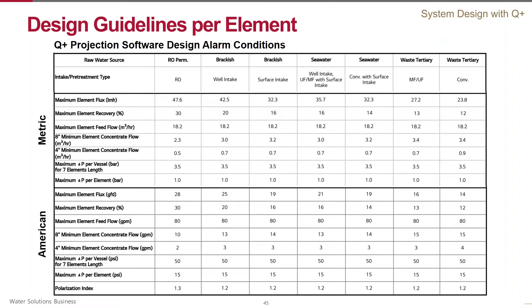While doing a system design, one should be cautious about individual elements not to exceed critical parameters such as maximum element flux, recovery, etc. This table summarizes LG design guidelines applicable for individual elements. Every time one or another parameter exceeds these recommendations, the software generates a warning. The goal of the designer is to come up with a system that does not have warnings.